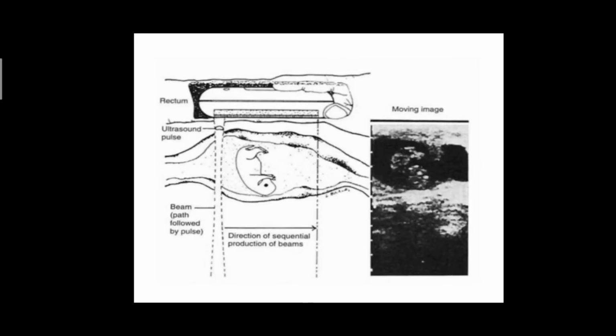In this image, there are major components of an ultrasound machine: an electric pulse generator, a transducer, a scan converter, and a video display. A high voltage electric pulse of a few microseconds causes the piezoelectric transducer to vibrate and convert electrical to mechanical energy, which is the ultrasound.